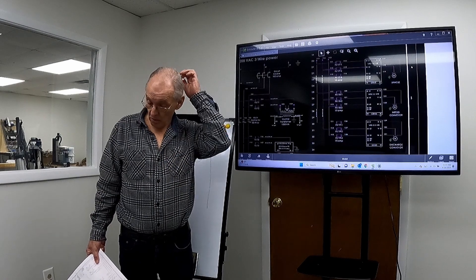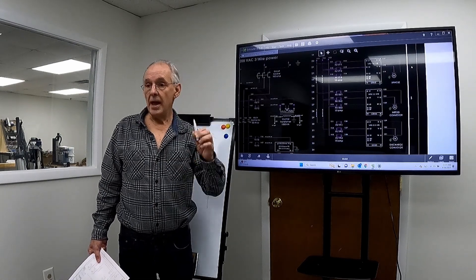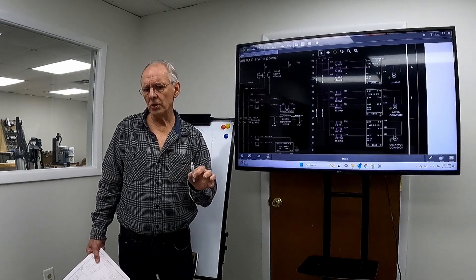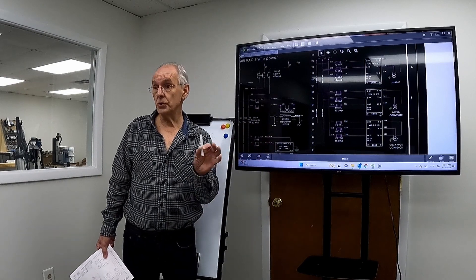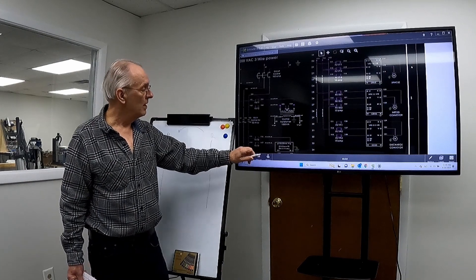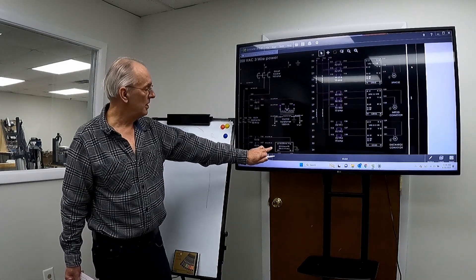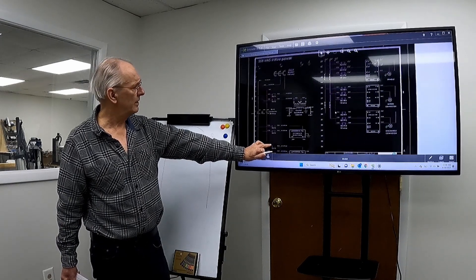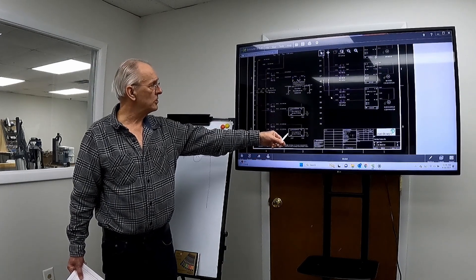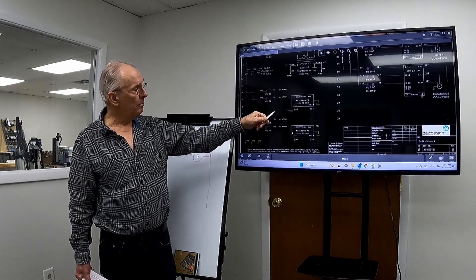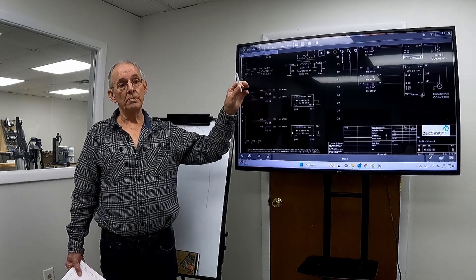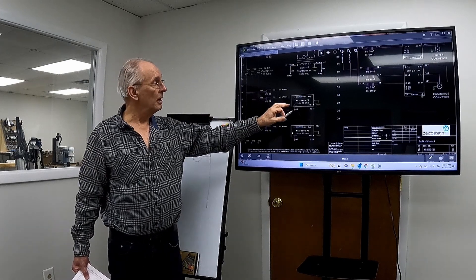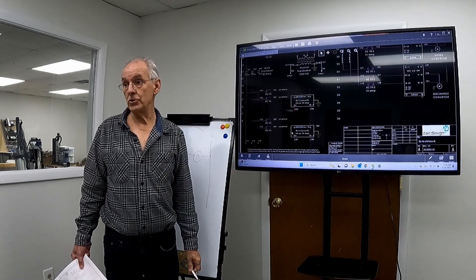So on this job, we have solenoid valves running air, and that's pretty much the only thing we have besides motors. And then there's also the servos, so we break the power to the servos. Now in the case here, you can see we have two power supplies for servos. So they come after the contactor, but if that contactor failed, these could still be energized, so the PLC control outputs that run the servo motors also get de-energized.